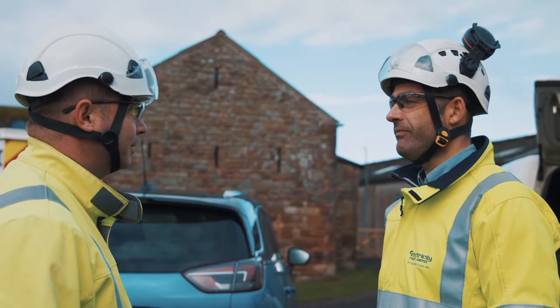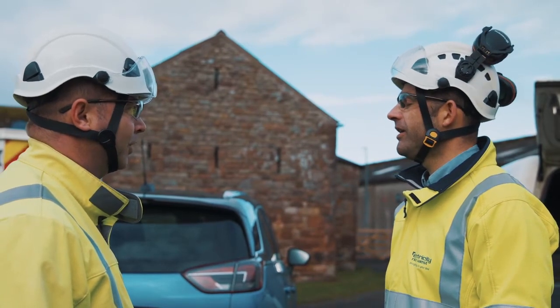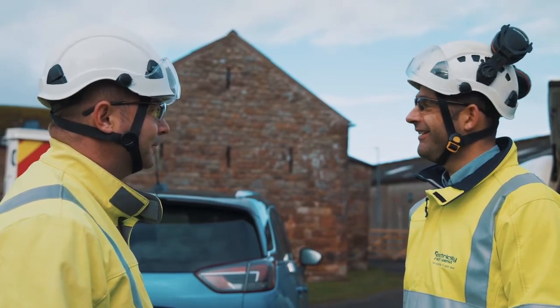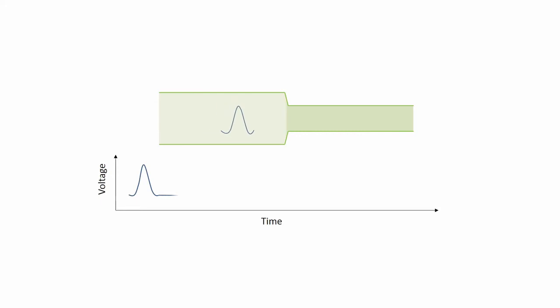The technologies deployed within Sentinel include impedance-based and voltage gradient technologies, as well as signal injection using TDR. This is the technology that will detect the low clearance lines. Effectively, it's a digital pulse that is constantly sent down the overhead line, and depending on the reflection of that signal, a change will be seen.